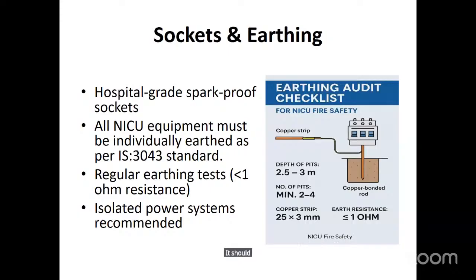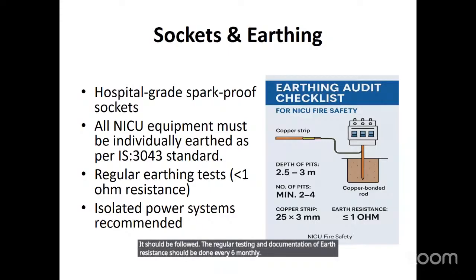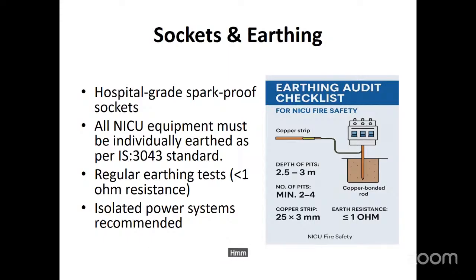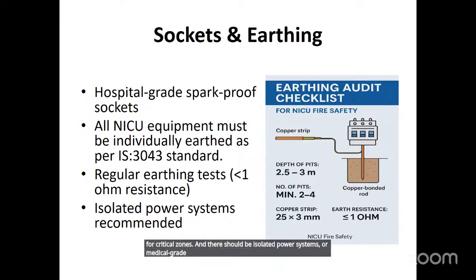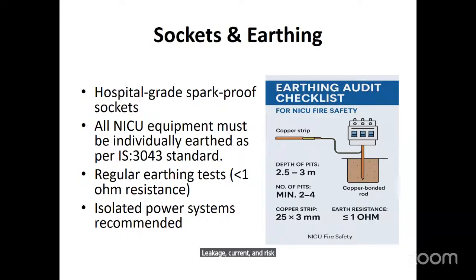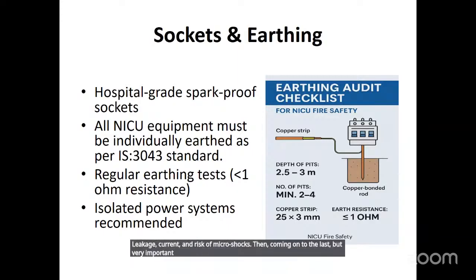It should be followed. The regular testing and documentation of earth resistance should be done every 6 monthly, and the resistance values should be maintained below 1 ohm for critical zones. And isolated power systems or medical grade isolation transformers are recommended for NICUs to minimize leakage current and risk of microshocks. Then coming on to the last but very important, very negligent point, that is storage and housekeeping. Next slide, please, sir.